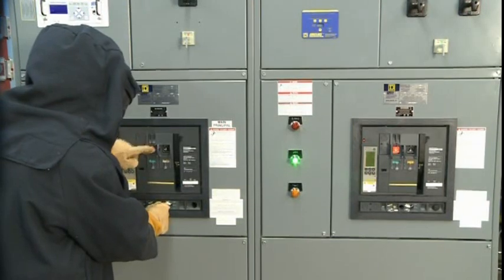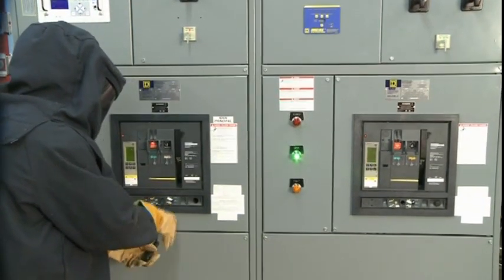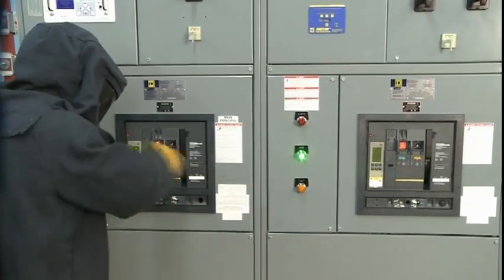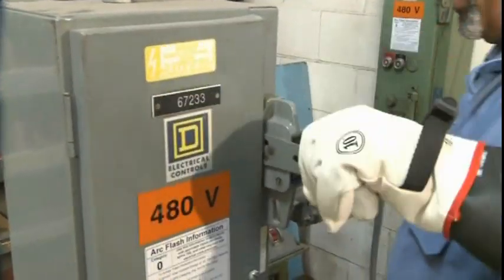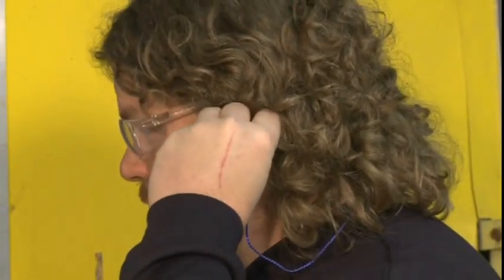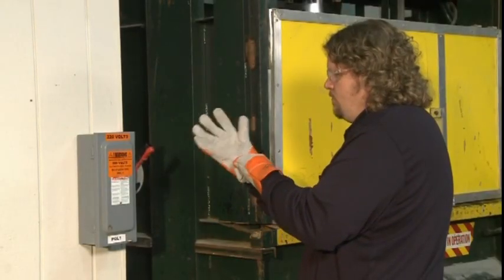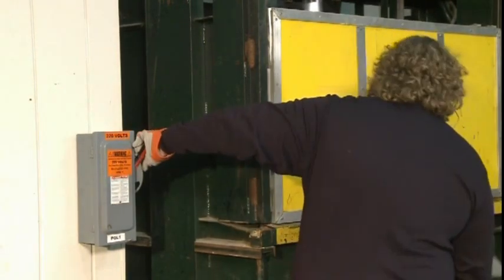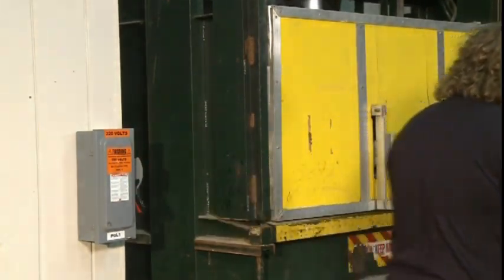Some examples of common tasks which are considered arc flash hazards include racking out a circuit breaker or operating an electrical disconnect switch. So does this mean that anybody who opens or closes a switch or resets a tripped circuit breaker must be a fully trained, qualified electrician? No, but it does mean that workers must be task qualified, meaning that they are qualified with respect to specific equipment and work methods, but remain unqualified for other electrical related tasks.